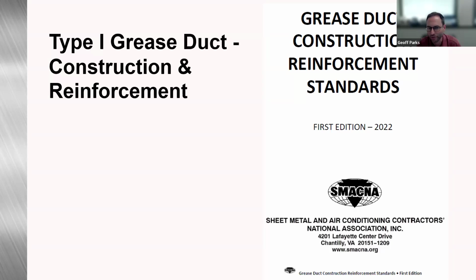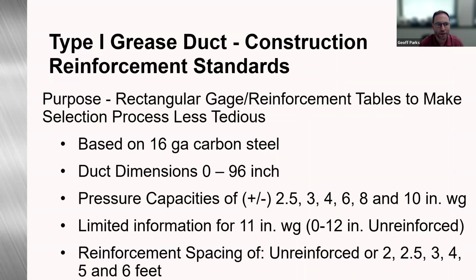And again, this one is solely for 16 gauge. The next edition, we're going to go in and add 18 gauge stainless steel. So the purpose of this construction reinforcement standard was to generate tables to make the selection process less tedious. Again, it was based off of 16 gauge carbon steel. Duct dimensions are going to be up to 96 inches.